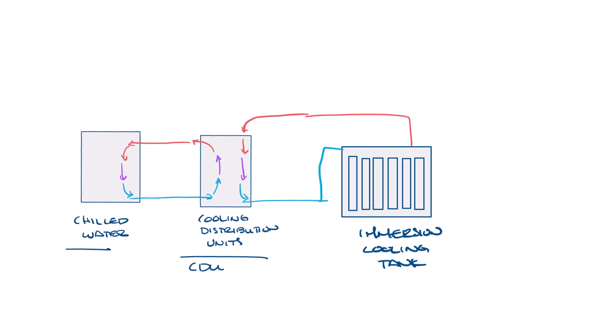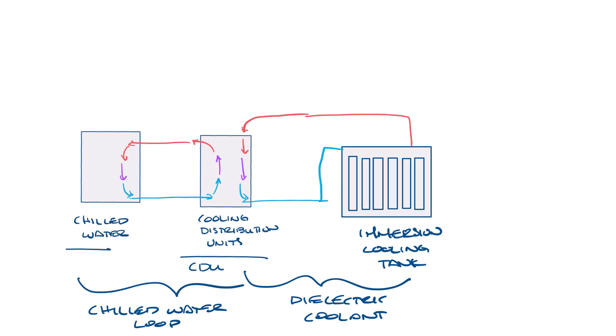So this is the tank with the servers inside, and let's connect the piping to the tank. Just like with the rear door heat exchanger or direct-to-chip system, there's a chilled water loop that goes to the cooling distribution unit, and then the CDU controls the coolant loop to the immersion tank.